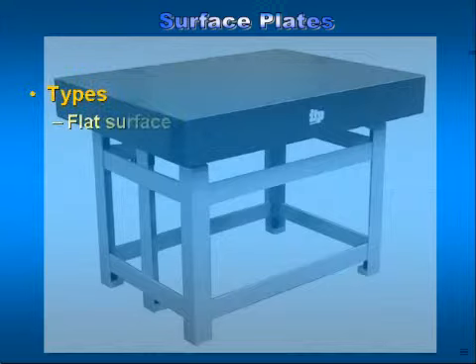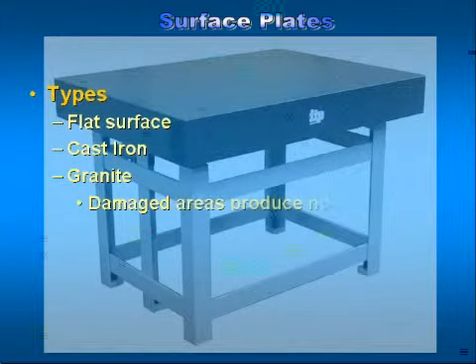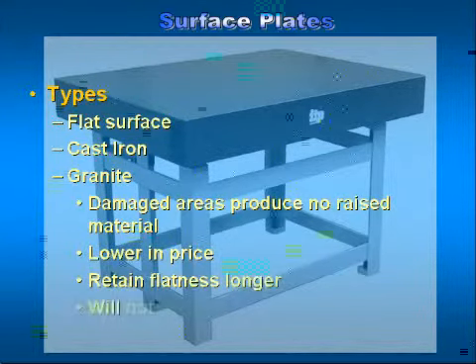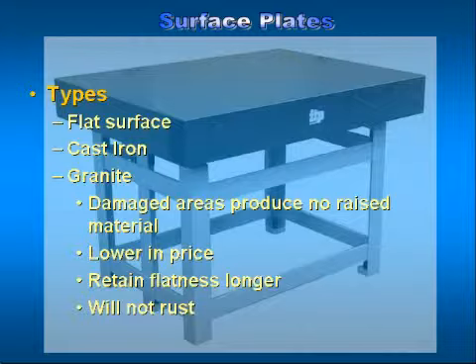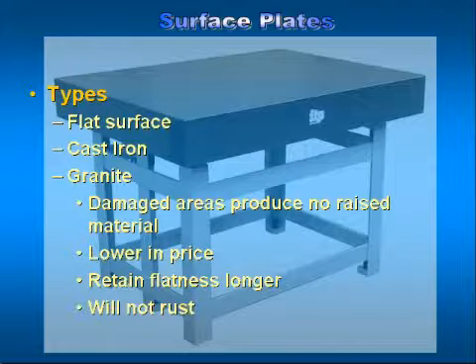There are different materials from which surface plates are made. Two of the main materials are cast iron and granite, which is a stone. Cast iron and granite surfaces have their good and bad points. For the purpose of this discussion, we will be talking about granite surfaces. The advantages of using granite surface plates include: damaged areas do not produce raised material, they are highly resistant to wear, they will not rust, they are resistant to damage from chemicals that may be present on parts being inspected, and they are resistant to any significant temperature expansion.